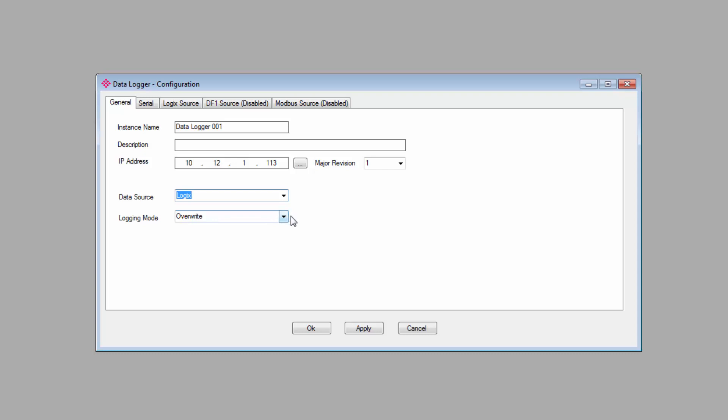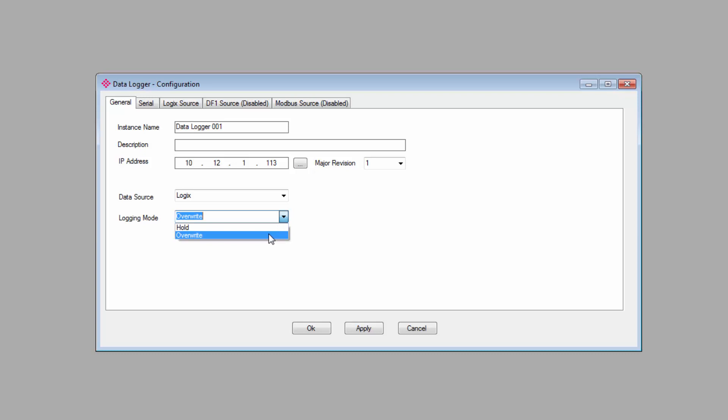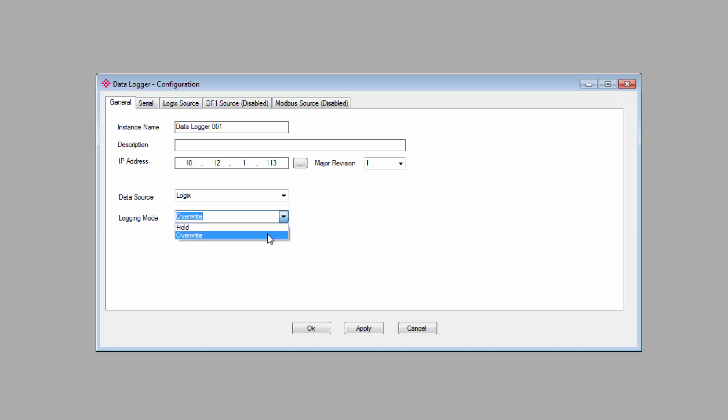We also have two logging modes, Hold and Overwrite. You're basically selecting what you want the PLX51 to do in the event that its database of more than 16,700,000 tags fills up. Hold will tell it to stop logging new data and just hold on to what it has. Overwrite will instruct it to go back and begin overwriting the oldest log data with new data. It depends on how you plan on using the PLX51. I'll select Overwrite.